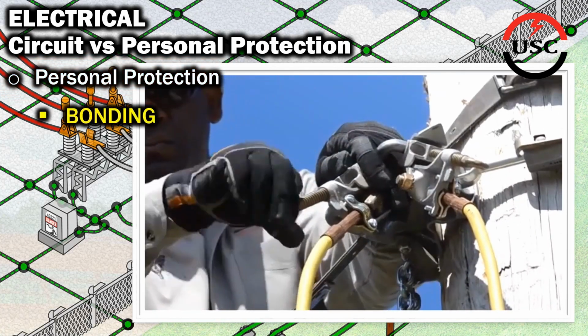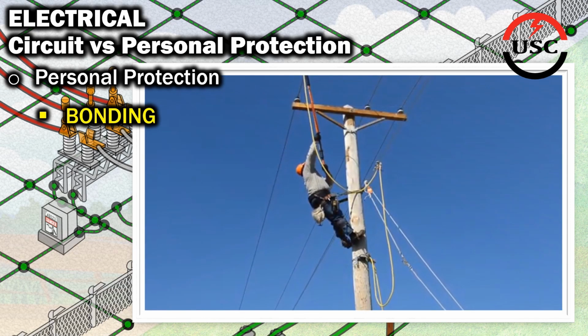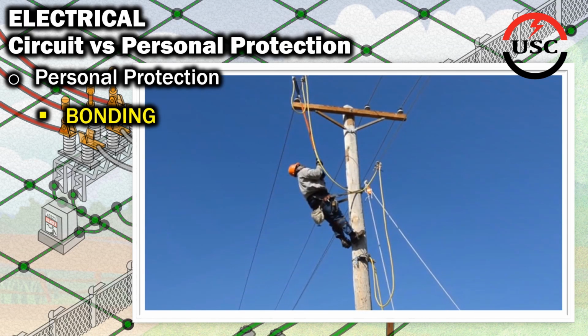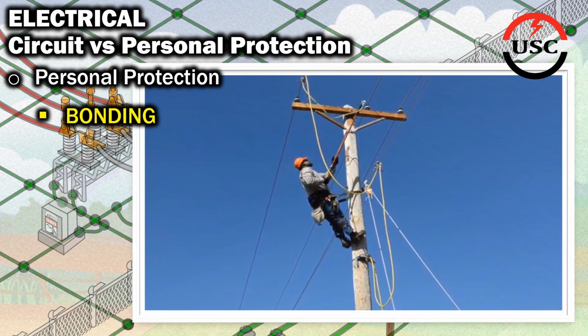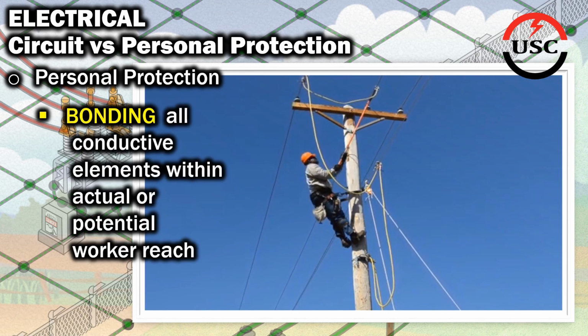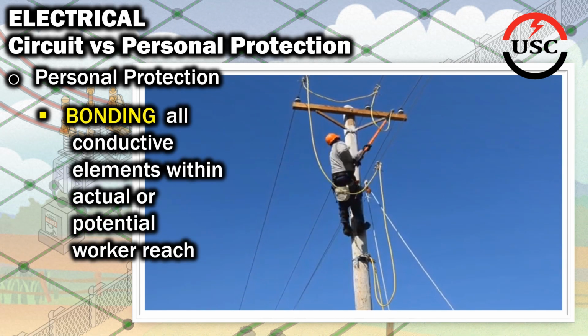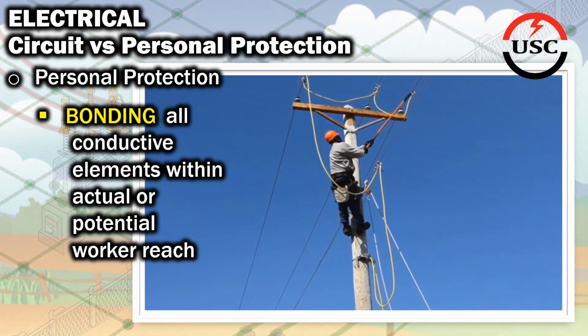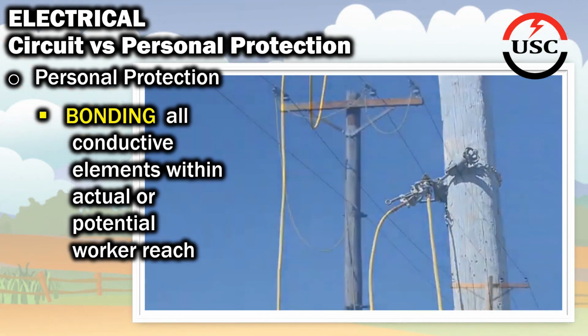Where circuit protection revolves around grounding, personal protection revolves around bonding. Personal protection serves the worker. Personal protection ensures that the worker is maintaining an equipotential zone of protection by eliminating two points of electrical contact through the bonding of all the conductive elements that may be within reach or inadvertent contact of the worker.